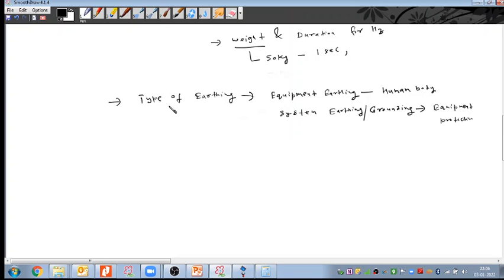So how did we do the earthing in those substations? In place of the three-phase fault current, we took the line to ground fault current only for the entire earthing calculations. So we did this ETAP study. We have not taken the total fault current. We have taken only the line to ground fault current, and that current only we used for the entire grounding or earthing calculations, due to the higher ground resistivity.